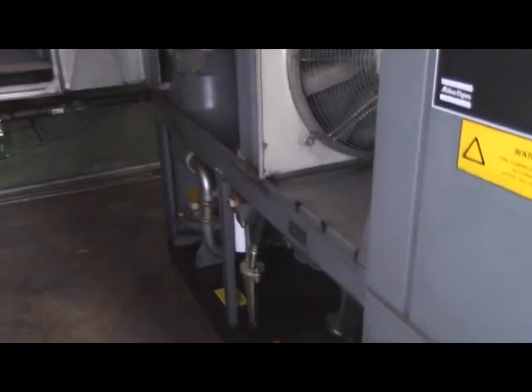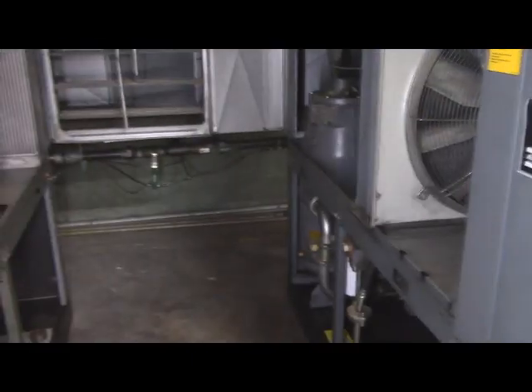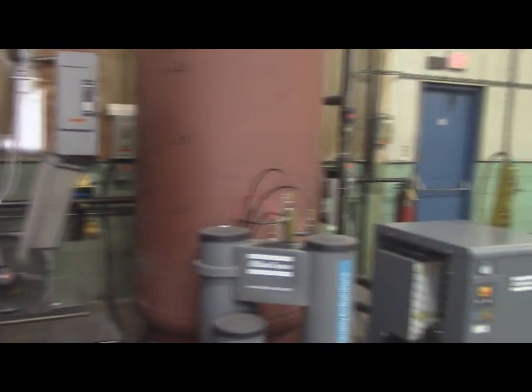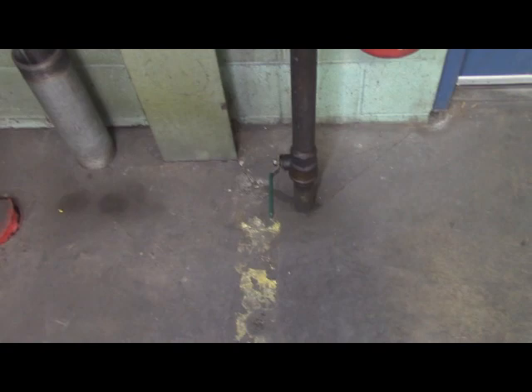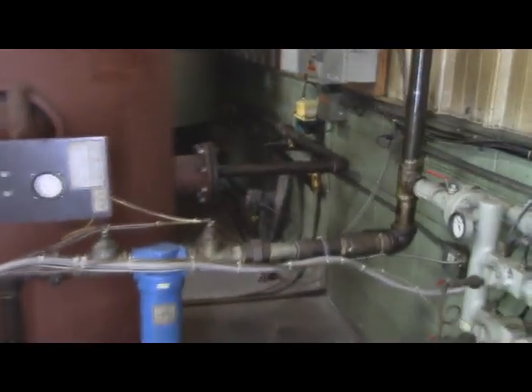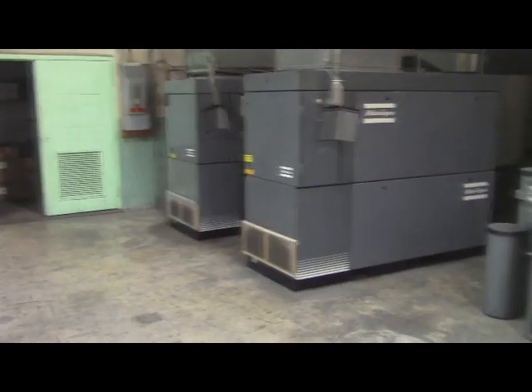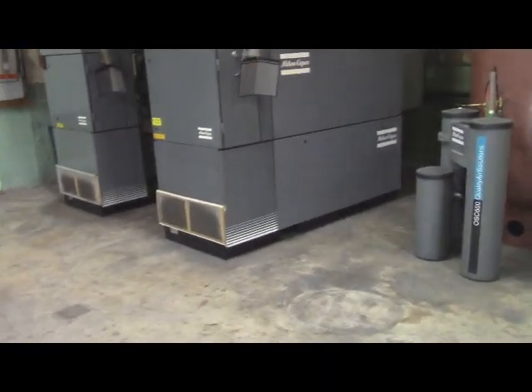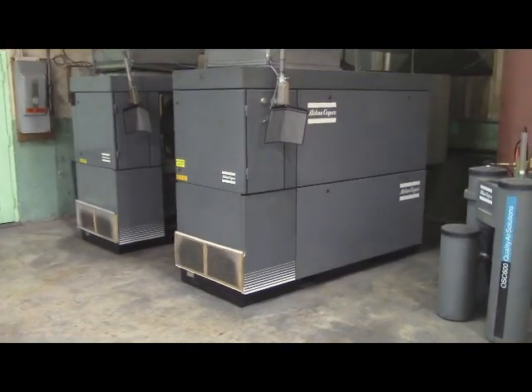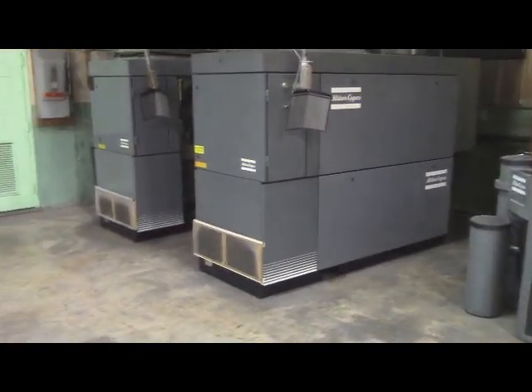That just shows you I have manual control over the system. We're not on automatic timer anymore because there's just a small skeleton crew working. But I keep this second compressor running so we have compressed air. When I start it up, it will charge this tank and give us air for most of the day with just that tank. So I have most of the shop closed off through this valve, sections 3 and 4, and down there's some other valves that close off the other sections. Okay, and that's it. That's a very nice setup, and it performs wonderfully. It'll stay running automatically according to demand requirements that is input by myself, and great machines.